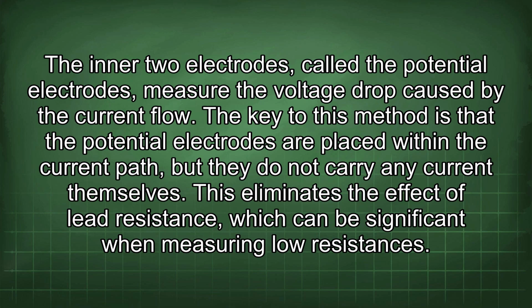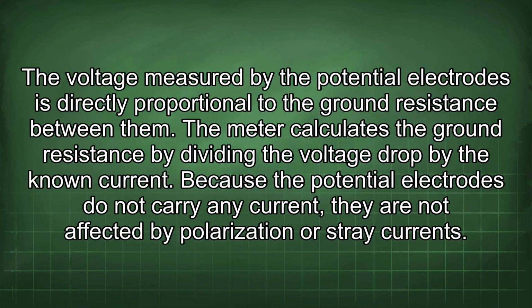The key to this method is that the potential electrodes are placed within the current path, but they do not carry any current themselves. This eliminates the effect of lead resistance, which can be significant when measuring low resistances. The voltage measured by the potential electrodes is directly proportional to the ground resistance between them. The meter calculates the ground resistance by dividing the voltage drop by the known current.